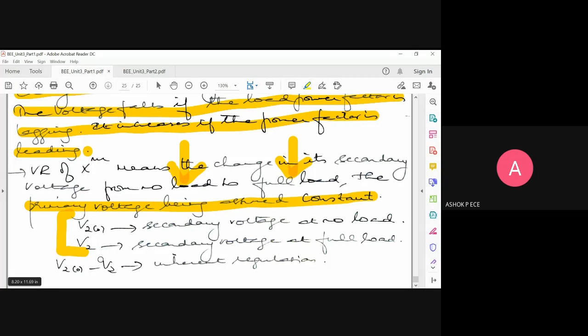It is called percentage regulation. Down means I'm going to measure with respect to V2 of 0. Up means I'm going to measure with respect to V2. The numerator is going to be the same in all cases. If you use the denominator as V2 of 0, it is percentage regulation downwards. If it is percentage regulation upwards, it is the same numerator divided by V2. If nothing is specified, you have to take it as percentage regulation downwards only. So (V2 of 0 minus V2) divided by V2 of 0. This is the standard formula we'll be using for percentage regulation downwards.